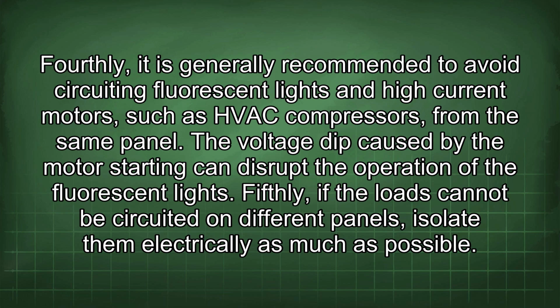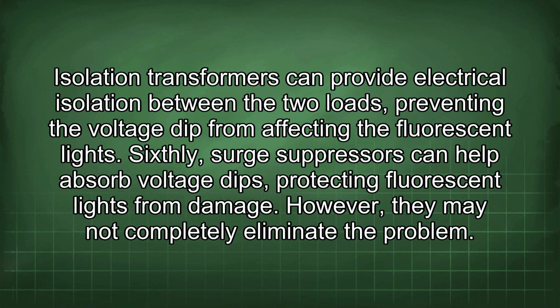Fifthly, if the loads cannot be circuited on different panels, isolate them electrically as much as possible. Isolation transformers can provide electrical isolation between the two loads, preventing the voltage dip from affecting the fluorescent lights. Sixthly, surge suppressors can help absorb voltage dips, protecting fluorescent lights from damage. However, they may not completely eliminate the problem.